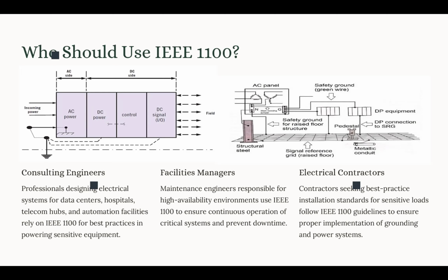Now, another group of people that use this standard are facility managers. Those facility managers are responsible for ongoing operation. This standard helps them to detect and mitigate issues proactively, so they don't need to wait for a problem. They have to be prepared beforehand. That could be monitoring grounding impedance and common mode voltage. We are going to talk about some criteria, like thresholds for proper grounding impedance and acceptable common mode voltage, that those facility managers should frequently check, making sure they are continuously meeting those requirements.